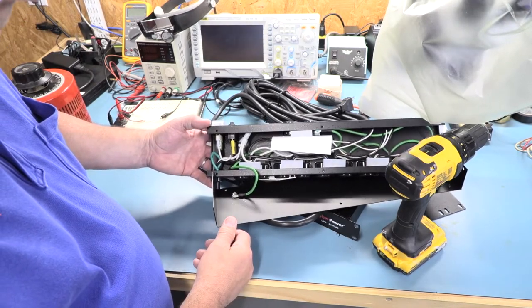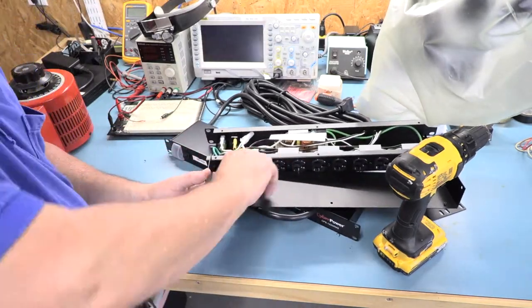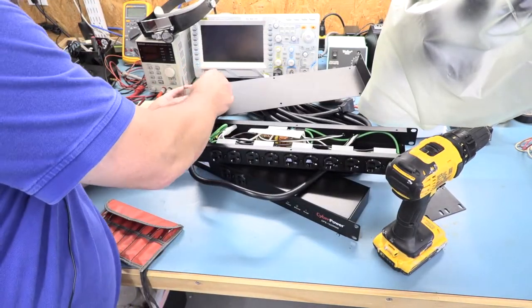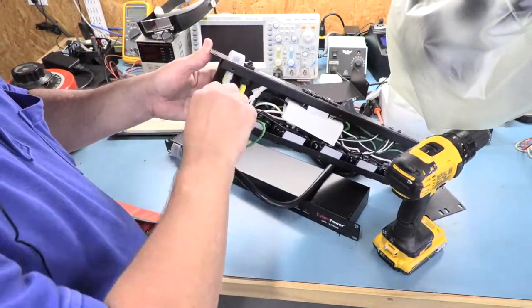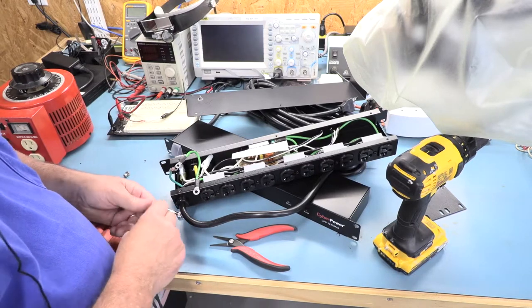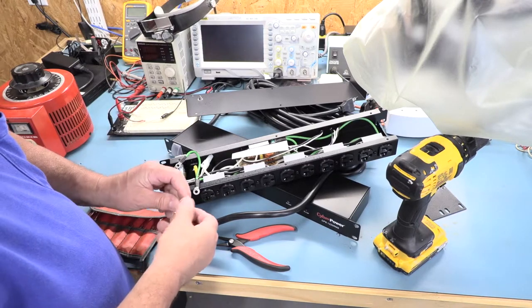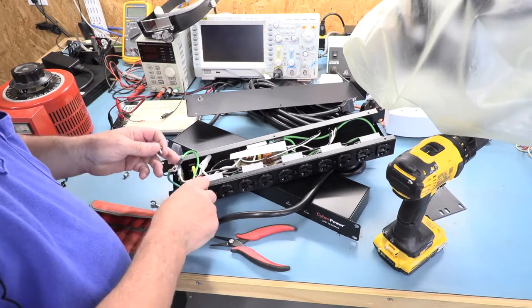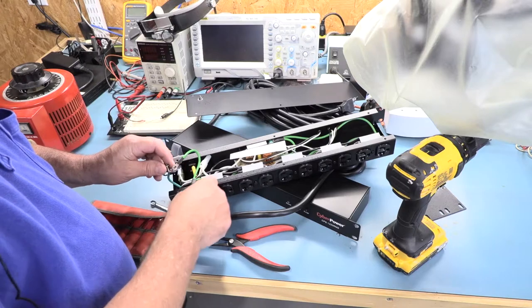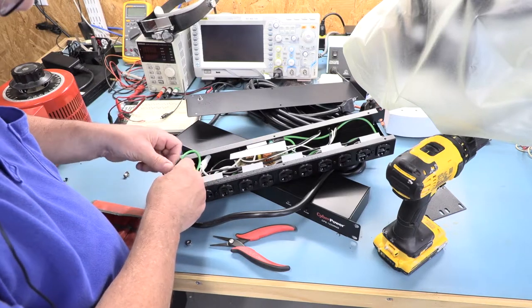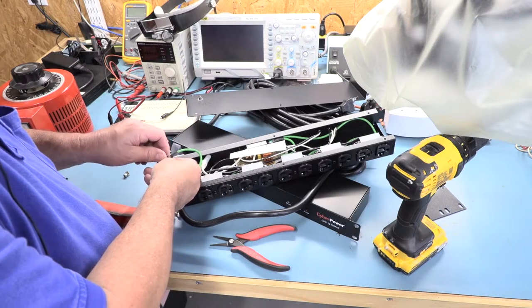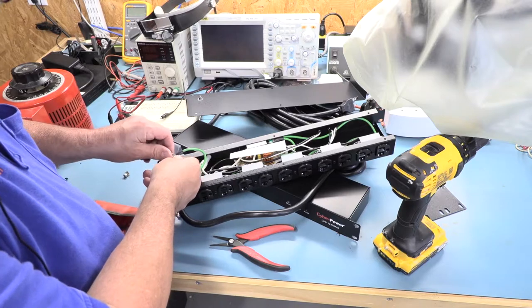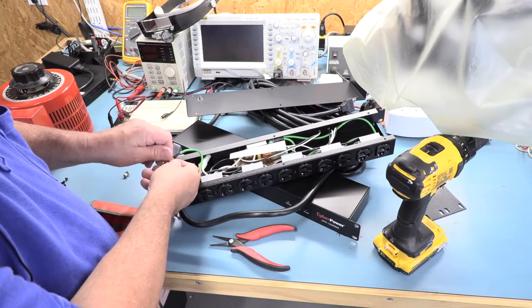We'll take both these off, tie them together, and then I'll tape them up real good so they don't contact anything else inside here. That should isolate this enclosure from the isolated ground. I don't think anything else is in here but we'll test it before we button it back up. I found a screw and a nut with a shake proof washer on it. I think I'll just tie these two together and tape this one up. I want to keep our isolated ground going to our receptacles.